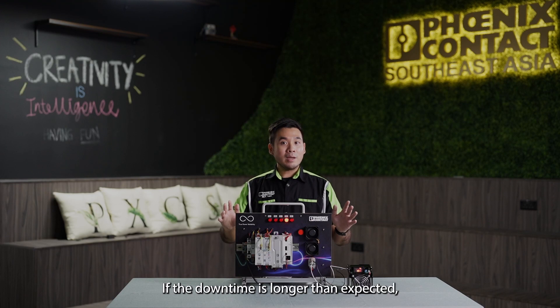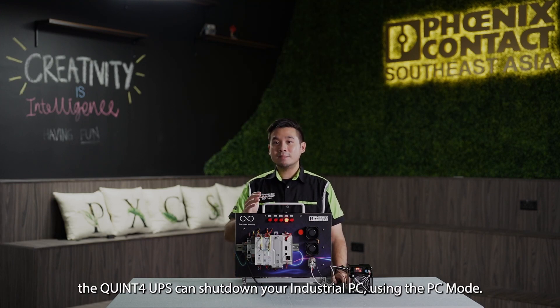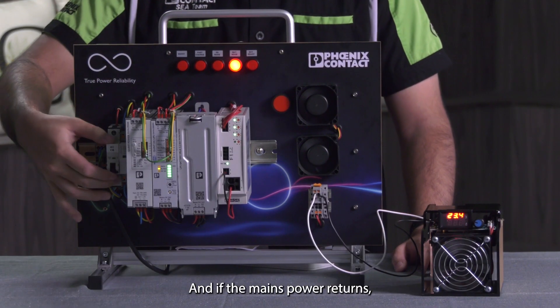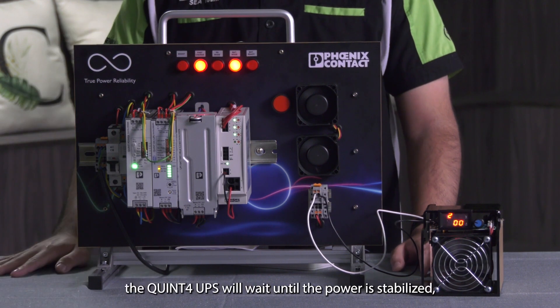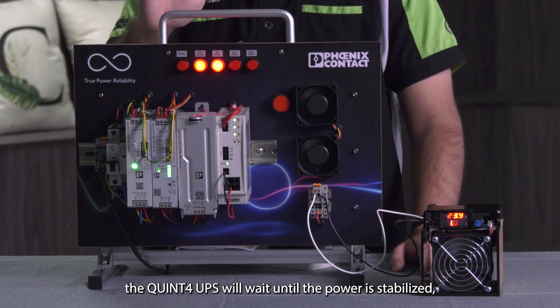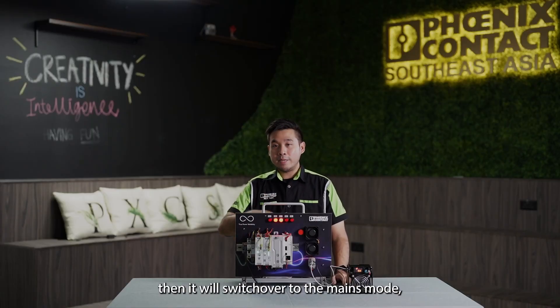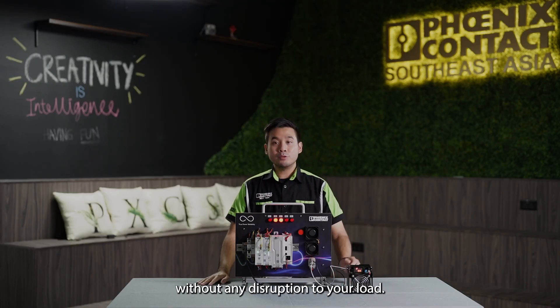If the downtime is even longer than expected, the QUINT4 UPS can also shut down your industrial PC using the PC mode. And when the mains power returns, the QUINT4 UPS will wait until the power is stabilized, then it switches back over to the mains mode without any disruption to your current load.